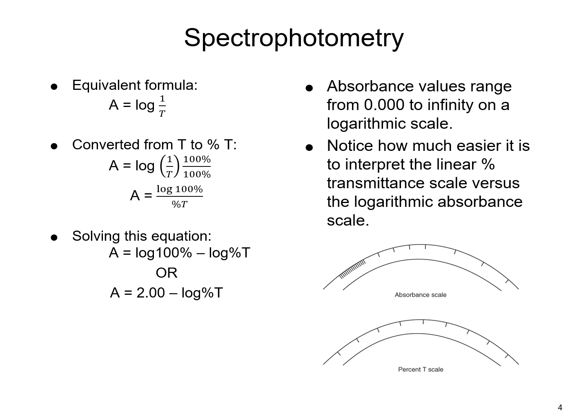In contrast to transmittance ratio, absorbance values range from 0.000 to infinity on a logarithmic scale. You can see from the meters that it is much easier to interpret something on a linear scale for percent transmittance versus a logarithmic absorbance scale. By convention, absorbance values are reported to the third decimal place, such as 0.000, whereas percent transmittance values are reported to the nearest tenth as a percentage.